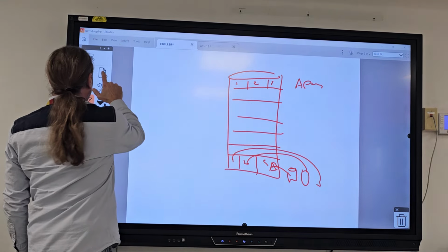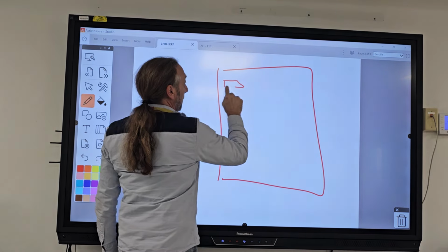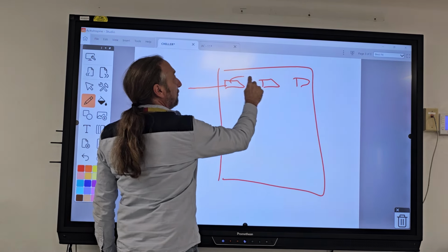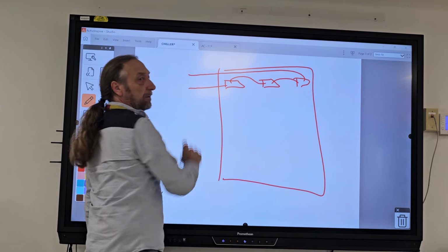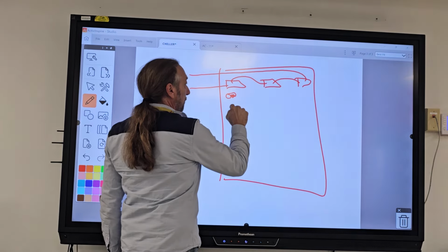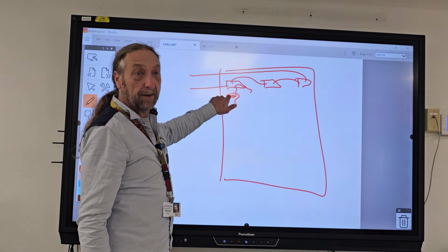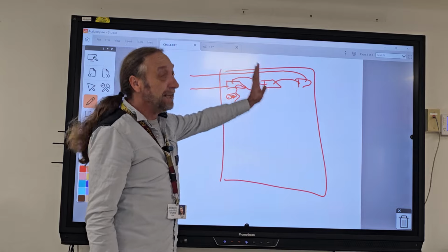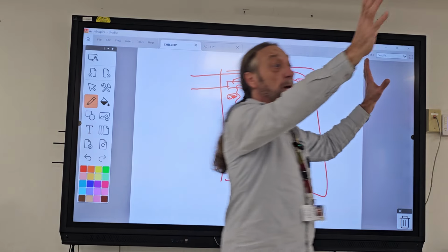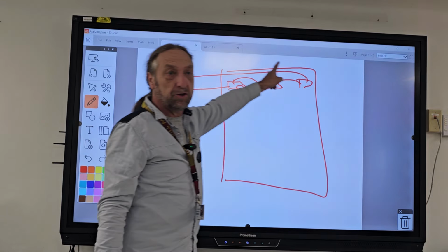So what do we do? On each floor, we have an evaporator, and it has water. That water flows to here, to here, to here, and then back. And each one has a fan to circulate the air, and a thermostat controls the fan for that evaporator. So for each room, you have a thermostat, a thermostat, a thermostat, and control the temperature of that room. So we have this water circulation going through.